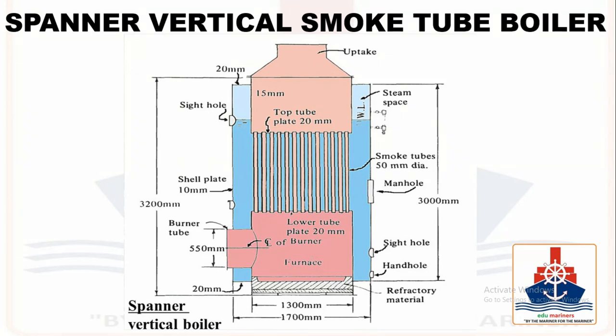In this boiler no stays are required for the outer shell or the internals. Only the flat tube plates require stay tubes for support, and this is done by stay tubes of plain sections expanded and then welded into the tube plates. This type of boiler can also be used as a composite boiler.